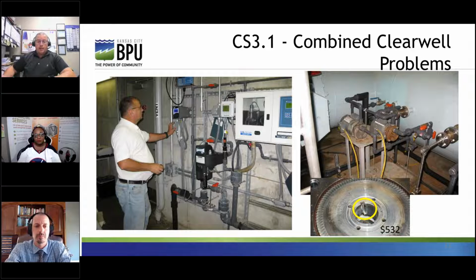Problems experienced in this area that we needed to address. Number 1, air in the sample stream caused pump impeller damage and turbidity problems. The turbidimeter would see the air in the sample, and that would cause false high turbidity readings. High turbidity readings cause the EPA KDHE turbidity requirements of less than 0.35 NTU and Partnership for Safe Water goals of finished water turbidity of less than 0.10 NTU to be higher. And the turbine regenerative pumps don't like to pump air. No pump designed for water really does.